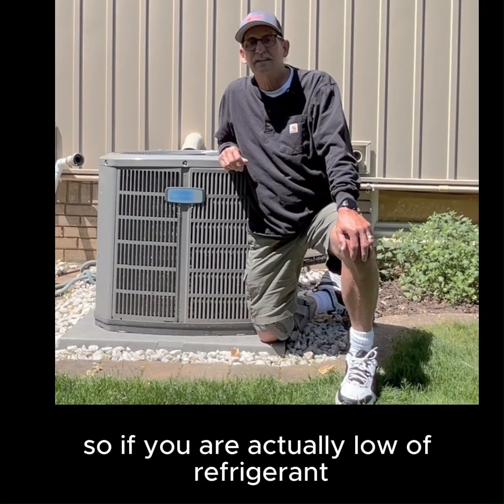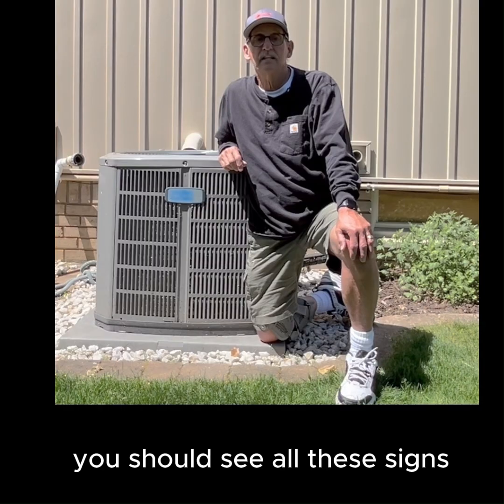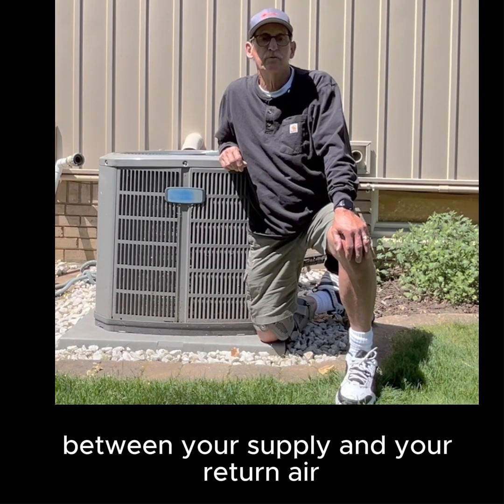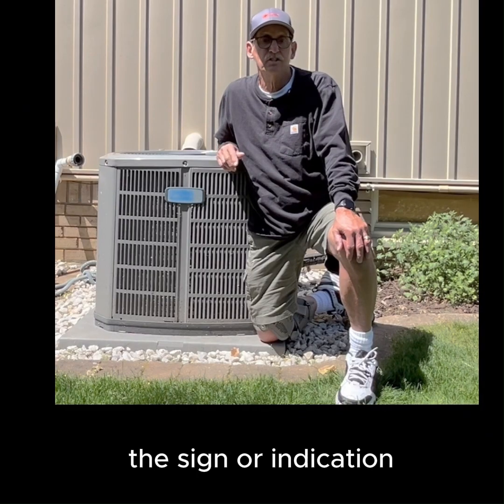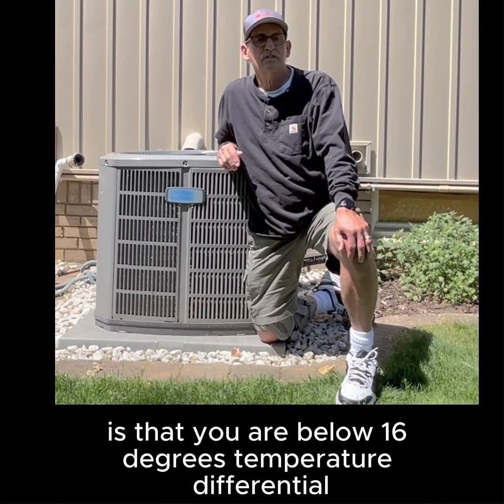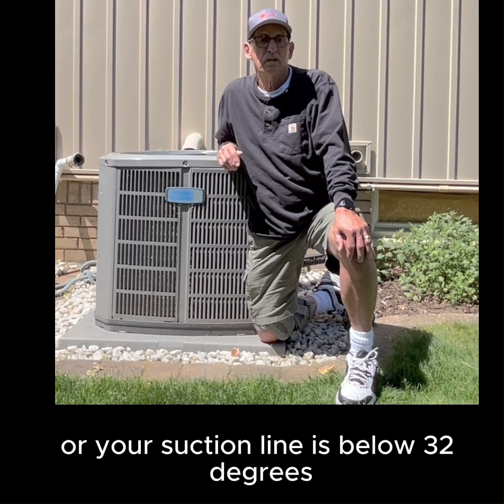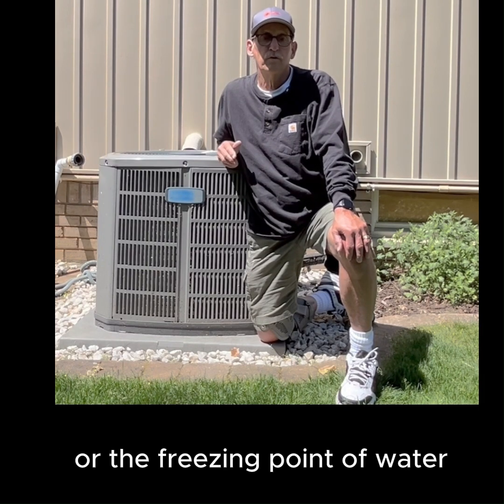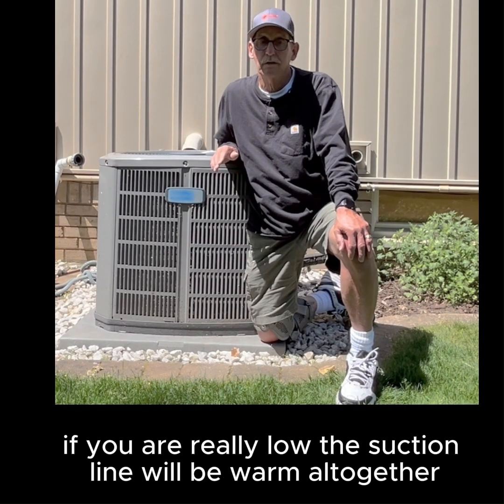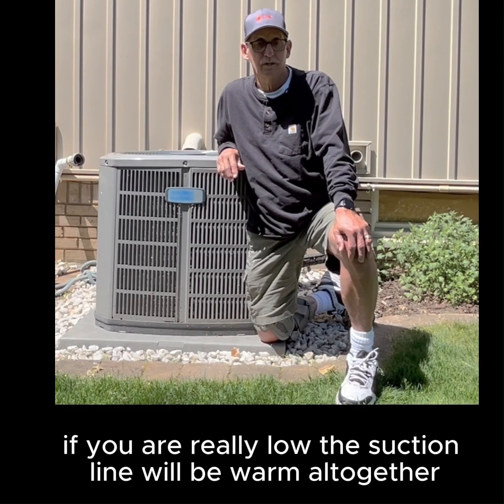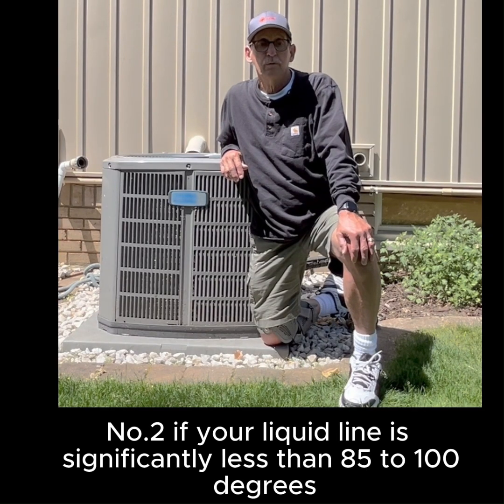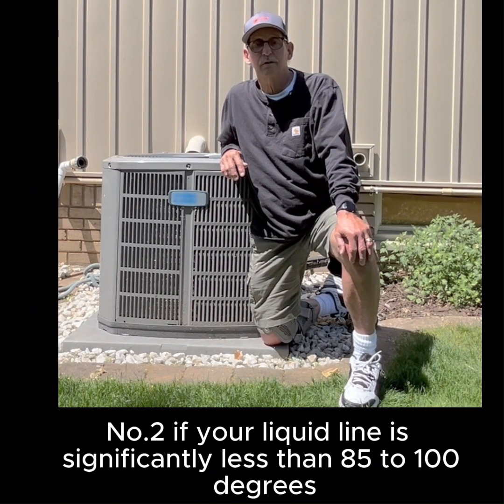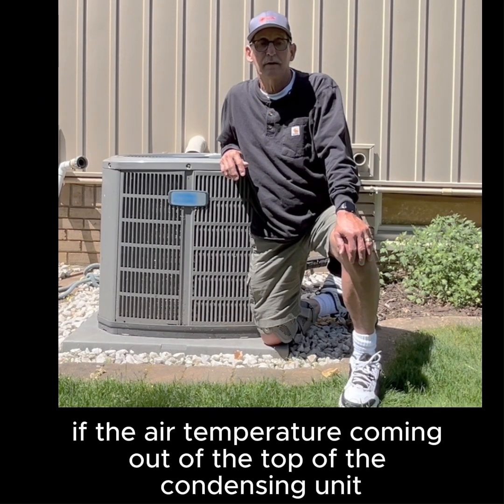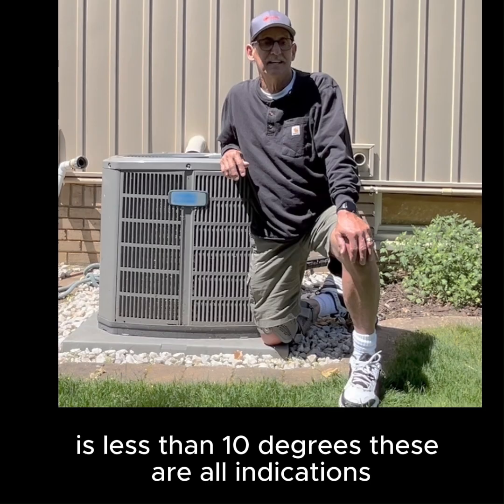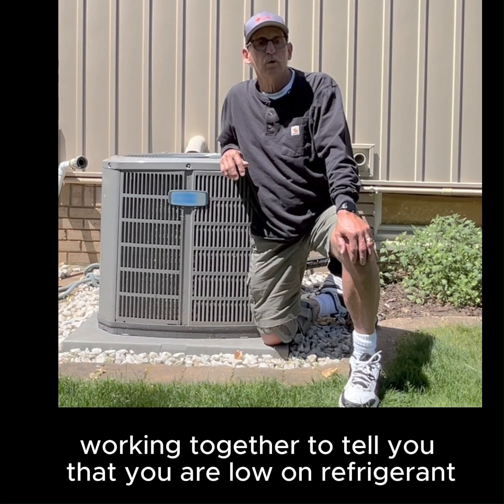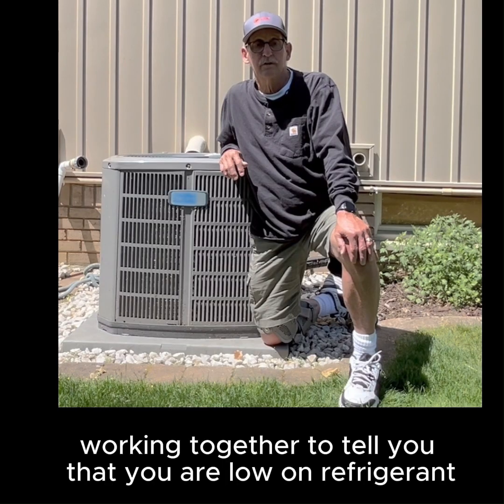So, if you are actually low of refrigerant, you should see all these signs through all of these temperatures between your supply and your return air. The sign or indication is that you are below 16 degrees temperature differential, or your suction line is below 32 degrees, the freezing point of water. If you are really low, the suction line will be warm altogether. Number 2, if your liquid line is significantly less than 85 to 100 degrees, and if the air temperature coming out of the top of the condensing unit is less than 10 degrees, these are all indications working together to tell you that you are low of refrigerant.